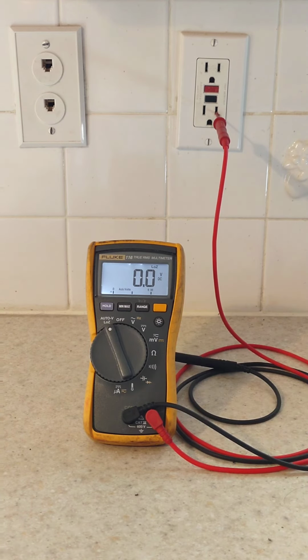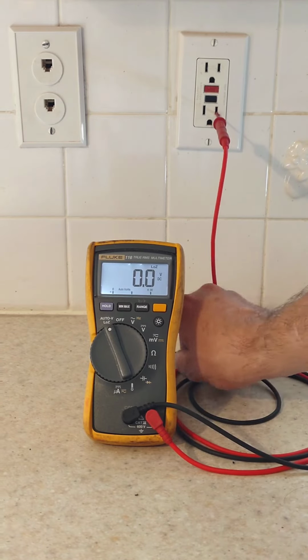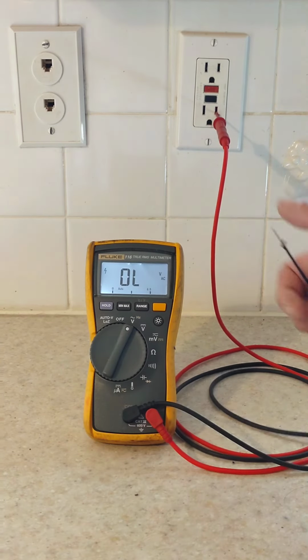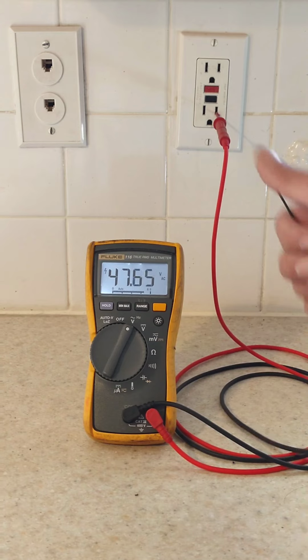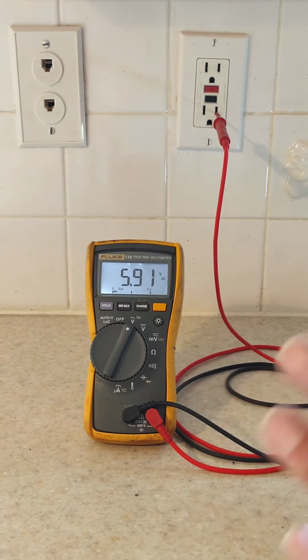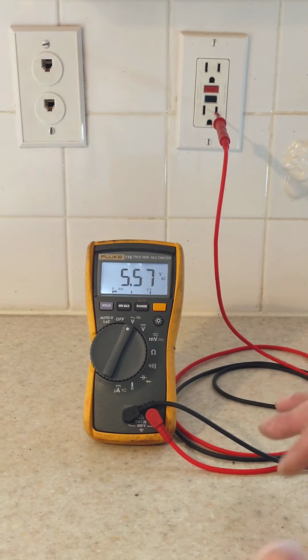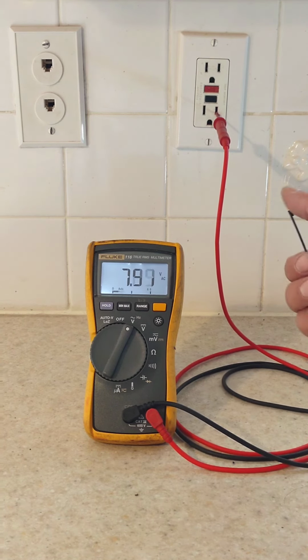So that can be a really useful feature, but knowing what we're looking at when we see a non-zero, non-120 volt voltage on our meters and one that changes as we're moving our probe around, that should be a red flag to every technician that what you're seeing is not a real usable voltage, it's a ghost voltage.